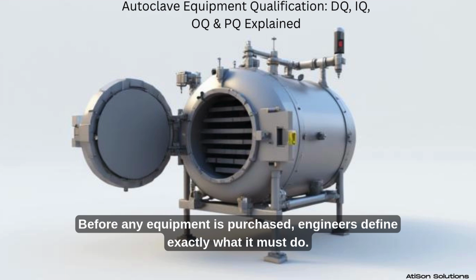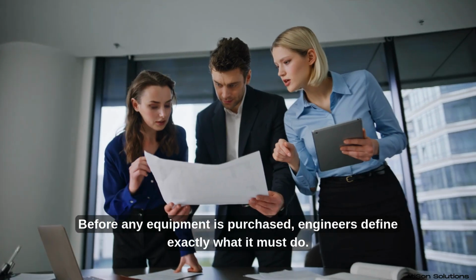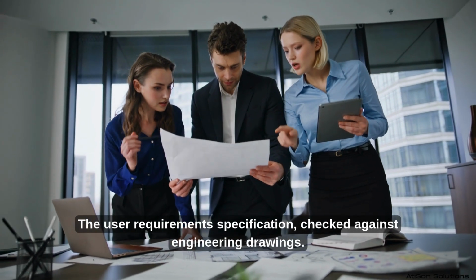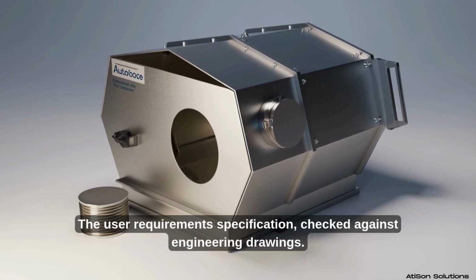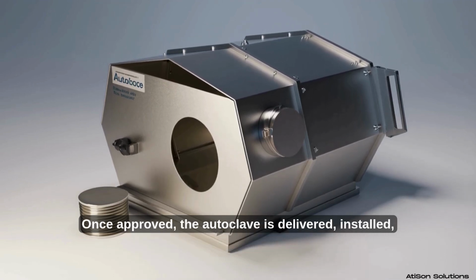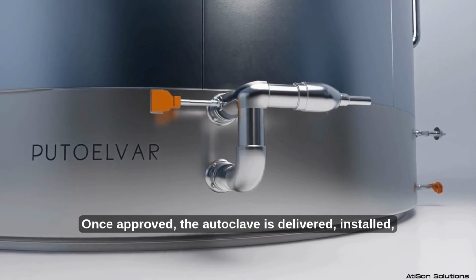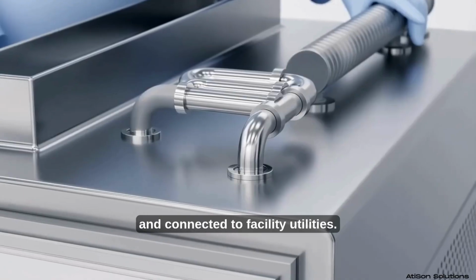Before any equipment is purchased, engineers define exactly what it must do: the user requirements specification, checked against engineering drawings. Once approved, the autoclave is delivered, installed, and connected to facility utilities.